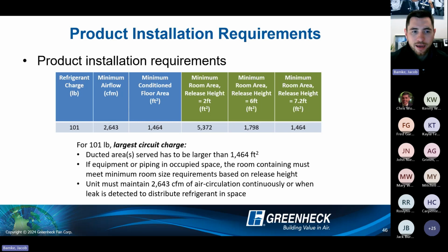And so in this case, if we had a 101 pound single circuit design, the minimum that you can serve as far as your space floor area is 1,464 square feet. Okay, so that's the first thing. If the equipment is in the space itself, then you have your piping in the occupied space. That room must meet the area in green as well.